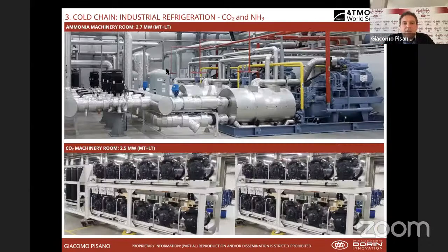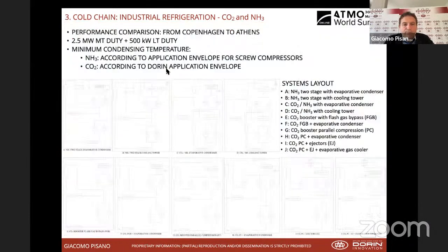This is another example for a 2.7 megawatt system between ammonia and CO2. So definitely CO2 brings in slimmer, smaller racks made with many compressors, okay, but still the footprint of the racks is pretty much small. So this brings in a lot of savings in terms of machinery room footage.